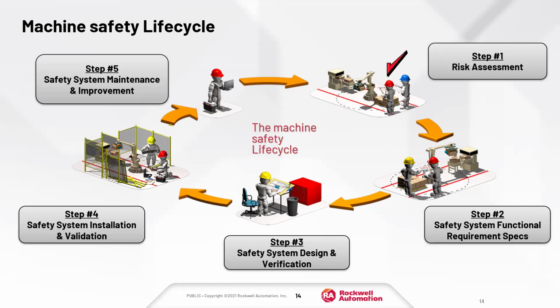This is the step I think a lot of people forget about. But again, code, when we go through those, the standards tell you that an e-stop should be exercised every month. If you have an e-stop, it's a mechanical device. You want to know it works. You want to hit that e-stop. You want to make sure that it did what you thought it would do, because now you know, okay, we're still safe. So testing, continuous testing of your things.